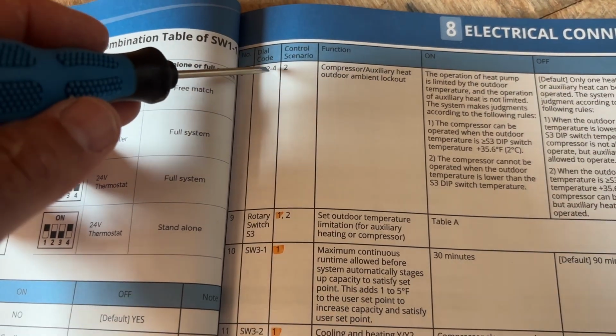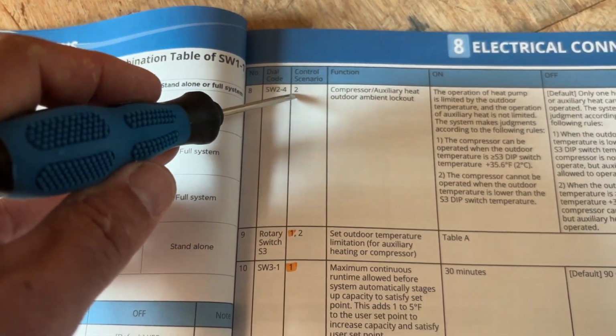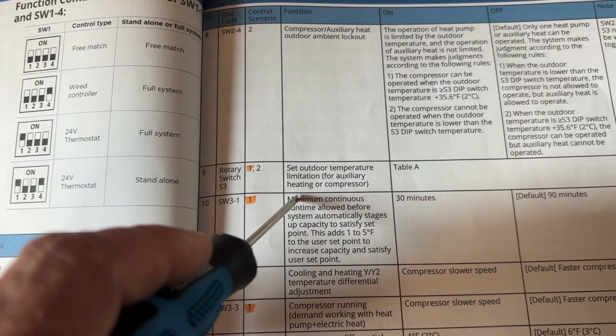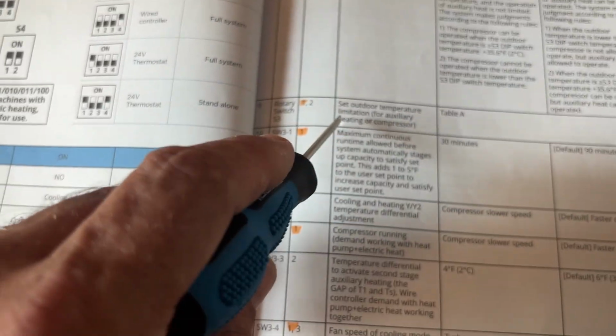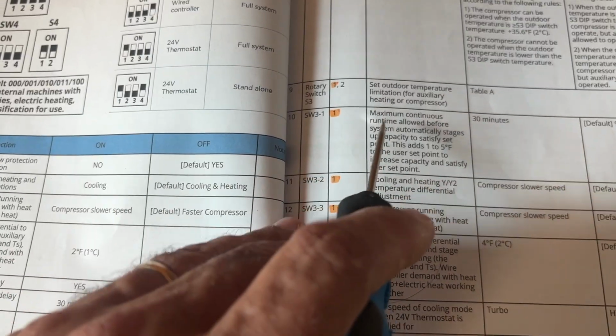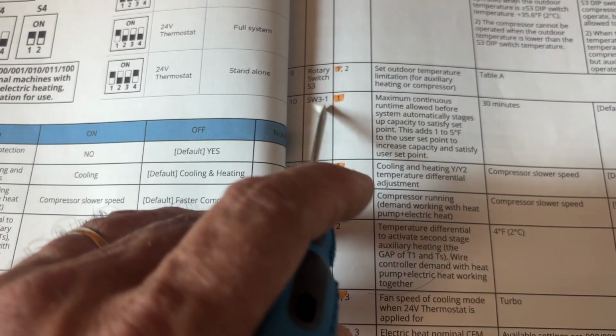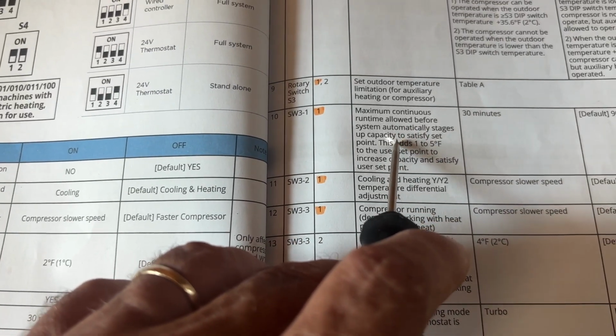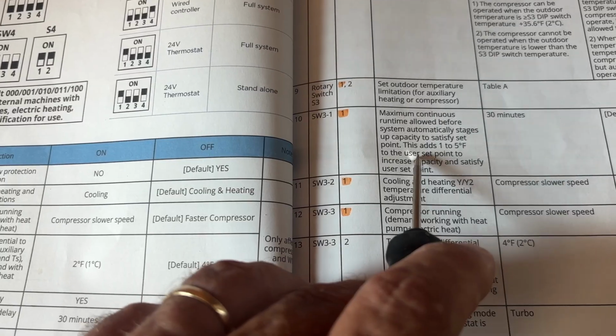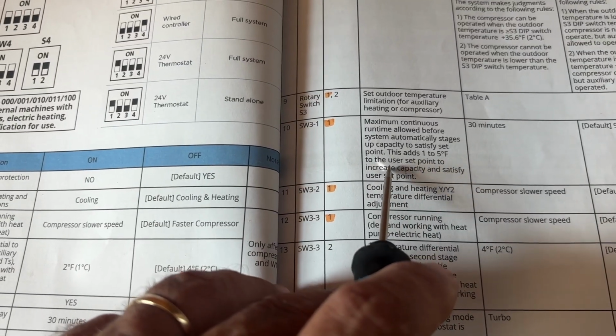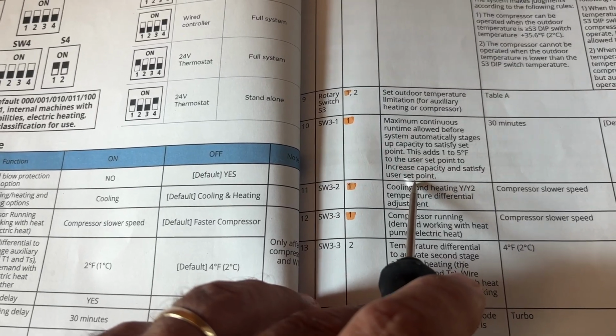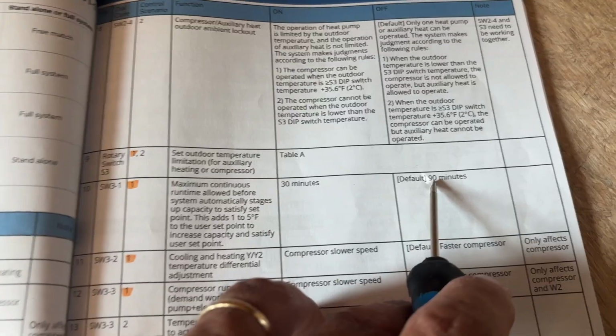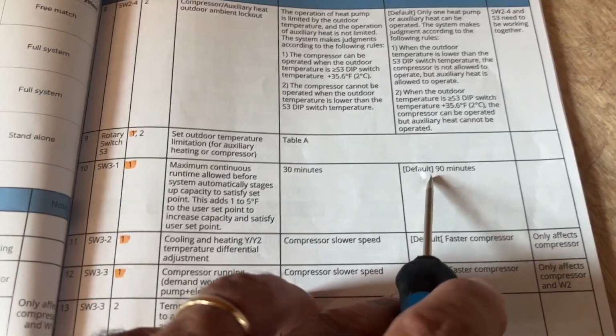going to use that. Over on the next page, we're looking at the 4th switch, SW24, that's control scenario 2, does not apply. Rotary switch, set outdoor temperature limitation for the auxiliary heating compressor, table A. I'm leaving that off. I'm gonna let the thermostat completely control the compressor and the auxiliary heat. SW31, maximum continuous runtime allowed before system automatically stages up capacity to satisfy the set point. This adds 1 to 5 degrees Fahrenheit to the user set point to increase capacity and satisfy the user set point. I'm leaving the default in here because it's more energy efficient to 90 minutes before it ramps up.